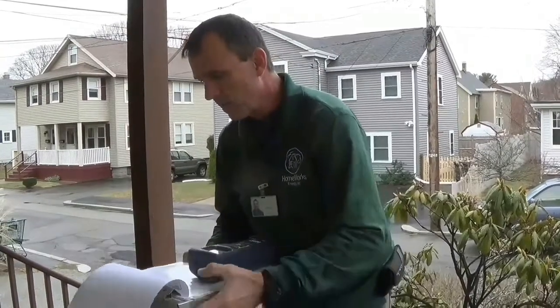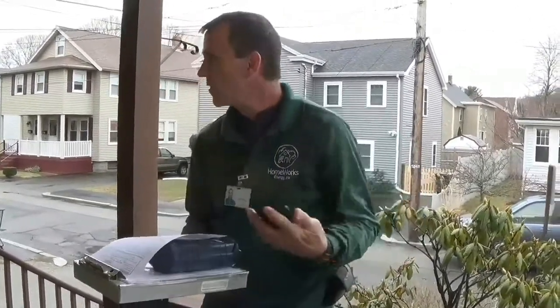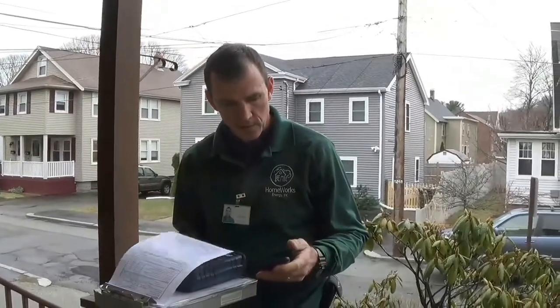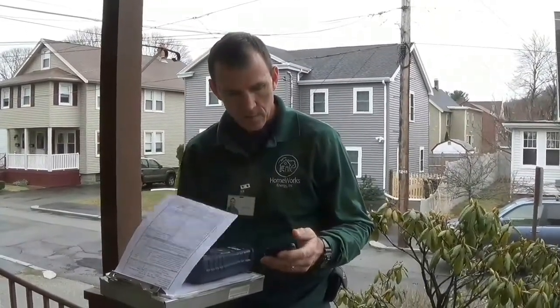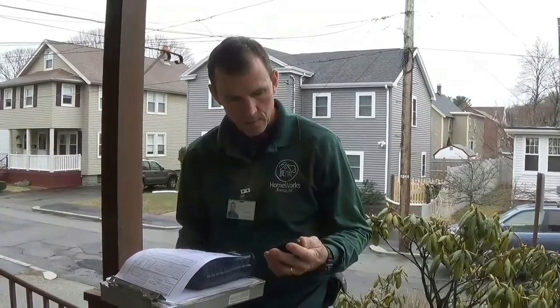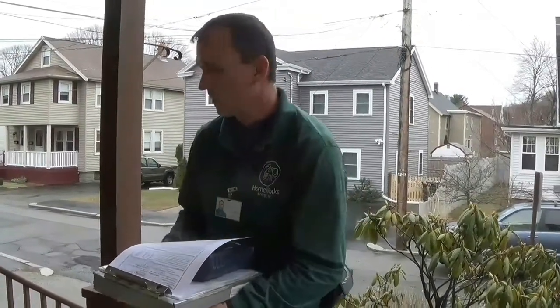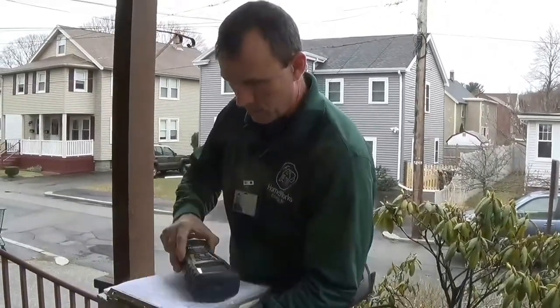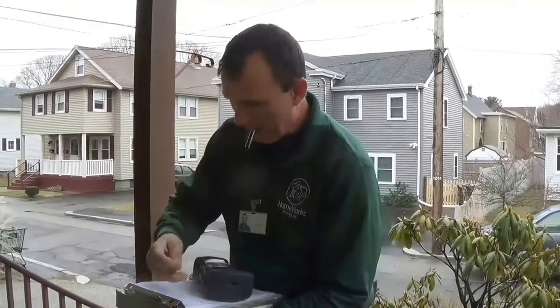And we are going to find out what the outside temperature is, because that's what we use to calculate our minimum draft pressure that we need for the systems that are atmospheric. And my temperature, 37 degrees. So then we use this formula.